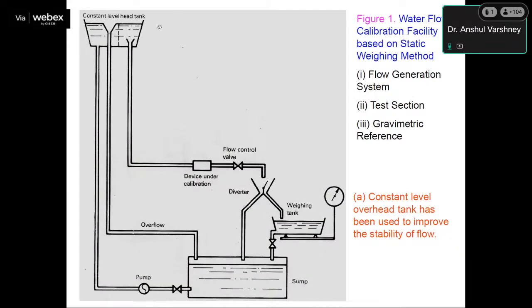So this is a schematic diagram of a water flow calibration facility based on static weighing. You can see there is a constant level overhead tank, and this is a weighing tank. This is the weighing scale, and this is the sump. Basically, water comes from the overhead tank to the tank, and there is a diverter. This is a very important part of the flow measurement system. Earlier, the water is flowing through this bypass line, through this diverter. When we divert flow into this weighing tank, water starts filling the tank, and when we stop filling, the mass of this water is measured. That mass is divided by the filling time, and you get the mass flow rate.